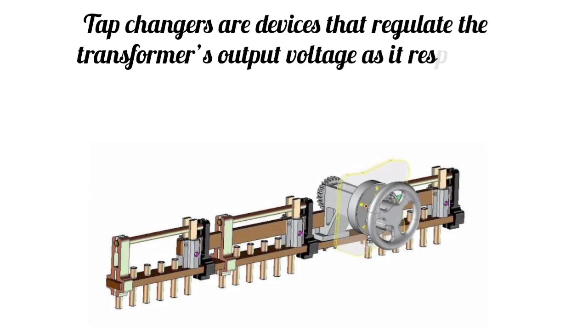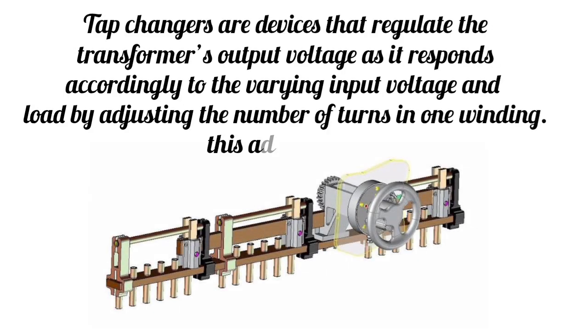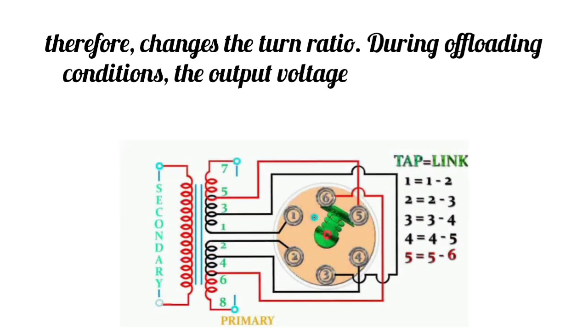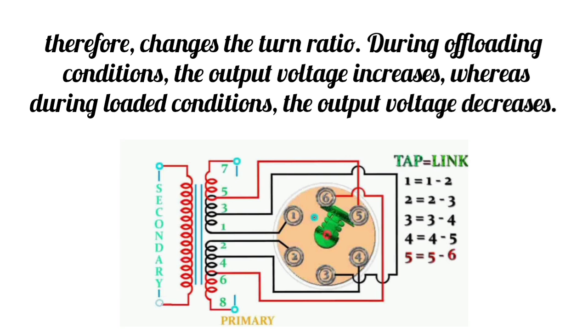Tap changer. Tap changers are devices that regulate the transformer's output voltage as it responds accordingly to the varying input voltage and load by adjusting the number of turns in one winding. This adjustment, therefore, changes the turn ratio. During off-loading conditions, the output voltage increases, whereas during loaded conditions, the output voltage decreases.